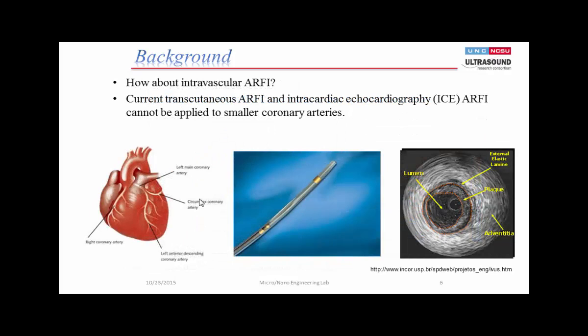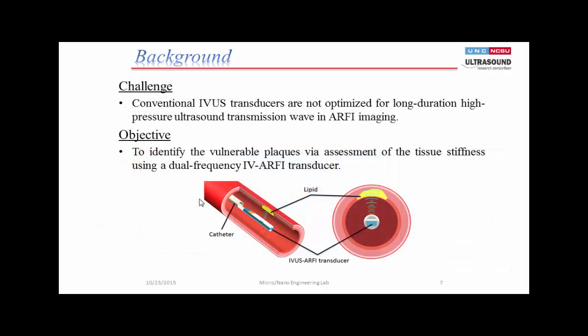The question is: can we apply that to intravascular ARFI? It's a similar concept. We know that transcutaneous ARFI imaging has been successful, and some commercial tools probably have ARFI imaging functionality. Considering IVUS, if you apply ARFI there, the first challenge will be the transducer design challenge.